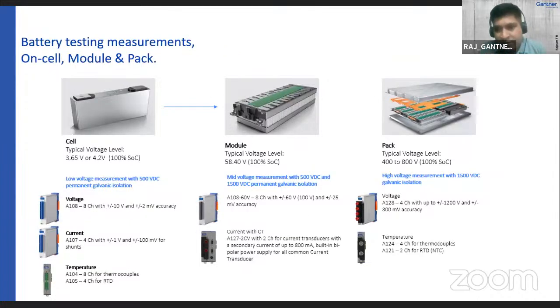So let us take the case of a battery. What are all the typical measurements that you make on a battery? We can divide the battery into three parts: the cell, module, and the pack. On the cell level, you are going to do low voltage measurements, in the range of 3.65 volt to 4.2 volt per cell. So you don't require a 1500 volt DC isolated module to do that. For that, we have our 500 volt DC isolated modules, where you can measure voltage, current, and temperature with an isolation of 500 volts. When it comes to the module, the total string voltage will come to around 58.40 volt.